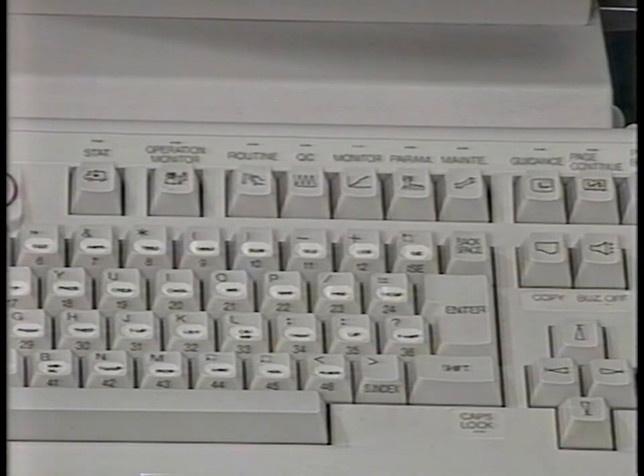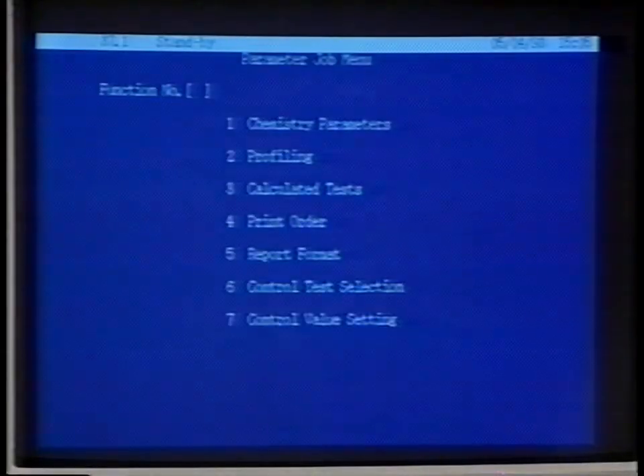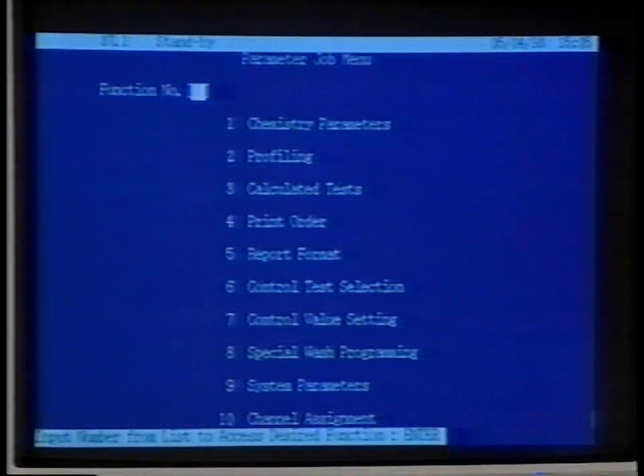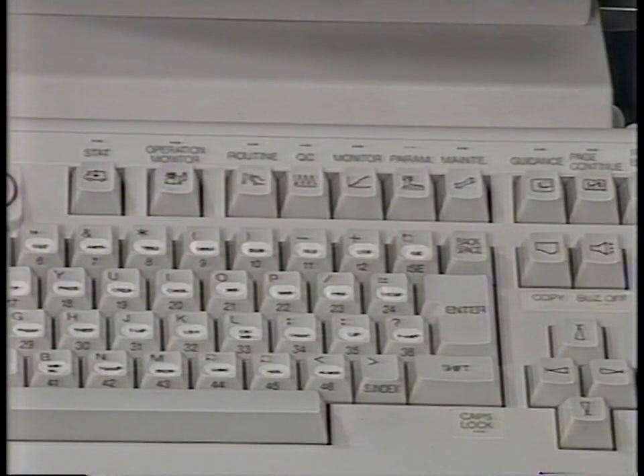The Parameter Job menu is selected by pressing the Parameter Job key. This menu allows you to enter chemistry parameters and profile names, as well as defining the tests to be included in those profiles. It's also used for programming formulas to obtain the results of calculated tests, such as LDL cholesterol or an AG ratio. In addition, this job allows you to customize the analyzer's printed reports by using the Print Order and Report Format screens. This is our final job key, the Maintenance job.